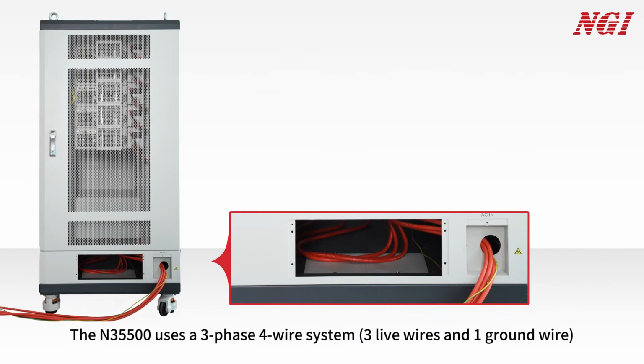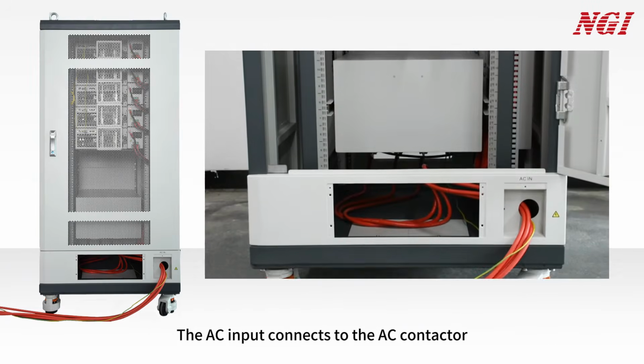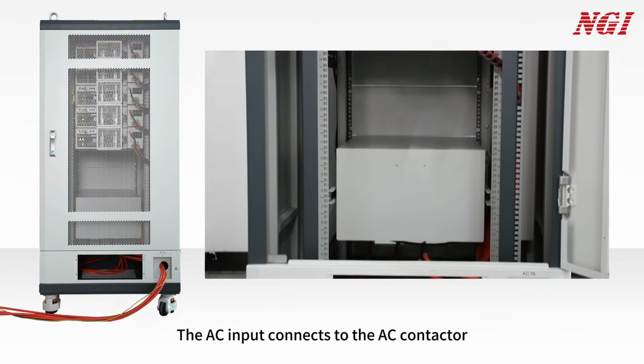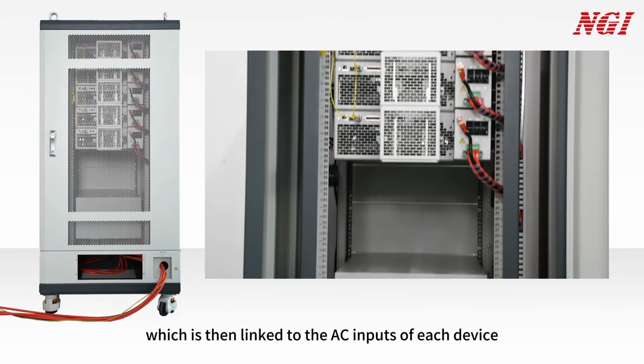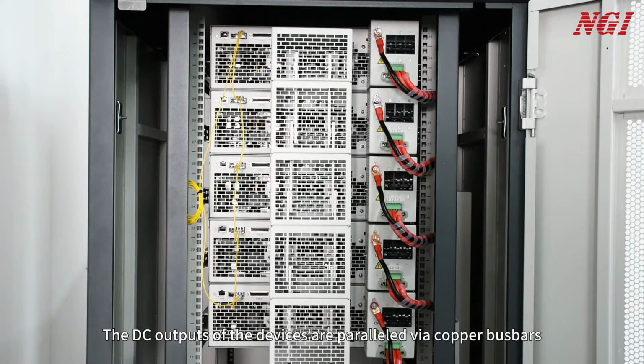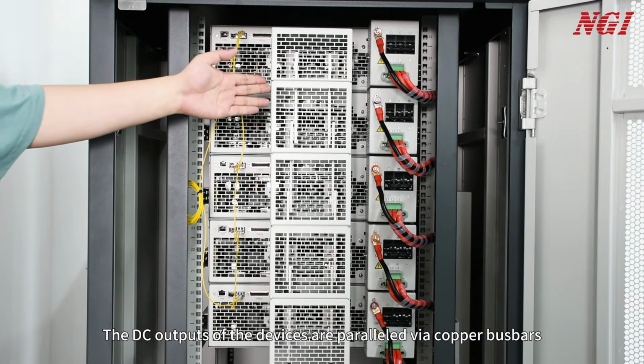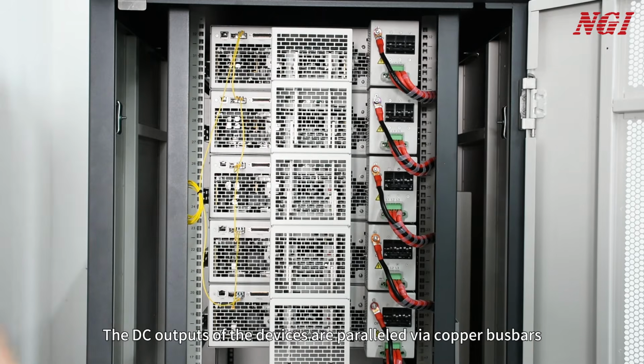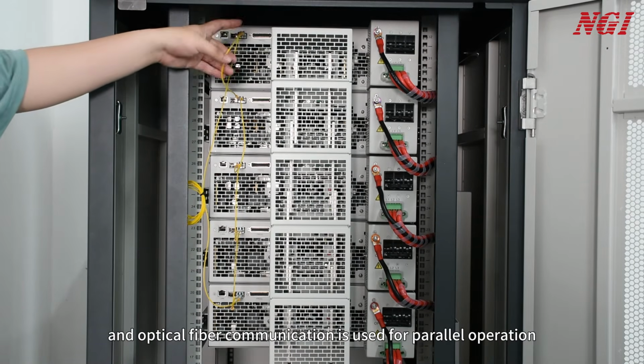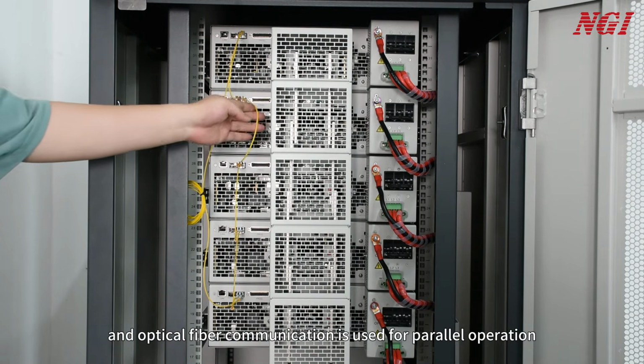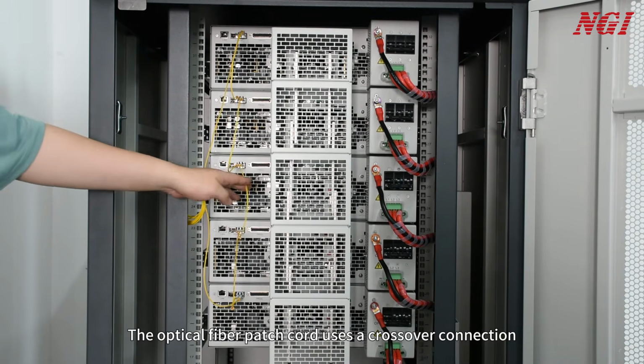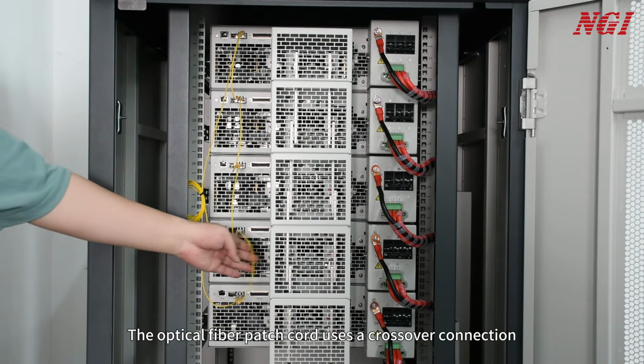The N35500 uses a 3-phase 4-wire system. The AC input connects to the AC contactor, which is then linked to the AC inputs of each device. The DC outputs of the devices are paralleled via copper bus bars, and optical fiber communication is used for parallel operation. The optical fiber patch cord uses a crossover connection.